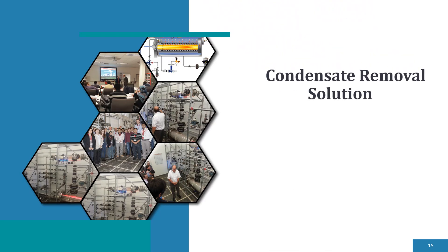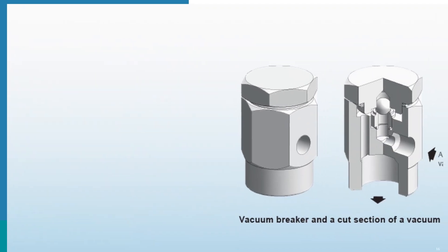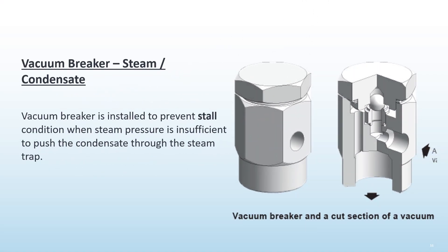The fourth topic is condensate removal solutions. Removal of condensate under all pressure conditions ensures stable temperatures. It also prevents bottom-end tube corrosion, potential water hammer, and freezing. This is a simple and efficient solution to a difficult problem without the need for expensive electrical pumps and sensors. The condensate system can be improved with a vacuum breaker, installed to prevent stall conditions when steam pressure is insufficient to push the condensate through the steam trap.